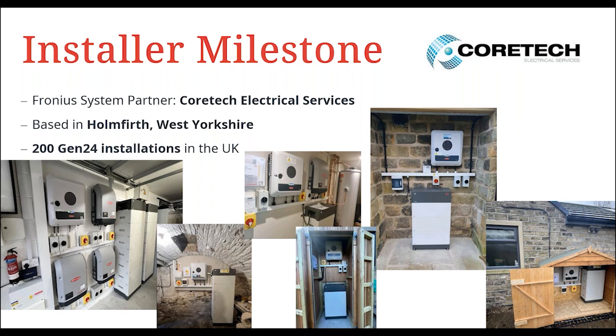Okay, thank you. Next question from James. For off-grid operation in areas with very unreliable grid, what is the maximum off-grid duty cycle that is acceptable? Yes, it's a very good question. We recommend using up to 20% of the lifespan being off-grid, and obviously then 80% of the lifetime of the product being grid tied. If you're in such an unreliable place, you may want to have a look at a solution which is more designed for permanent or mostly permanent off-grid solutions, such as from Victron. So we work very closely with Victron, partnering them for off-grid solutions, which may be more suitable for those sites where you're off-grid most of the time.